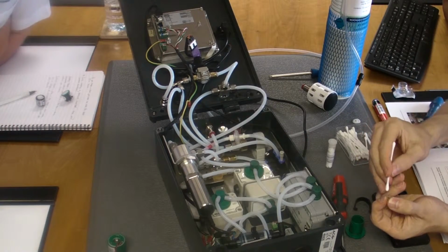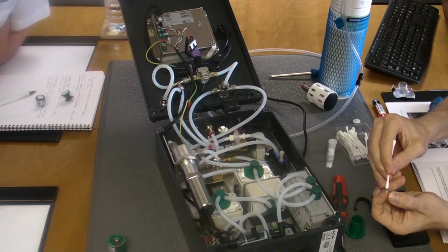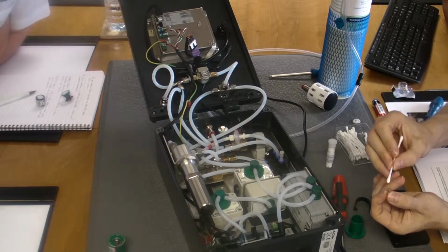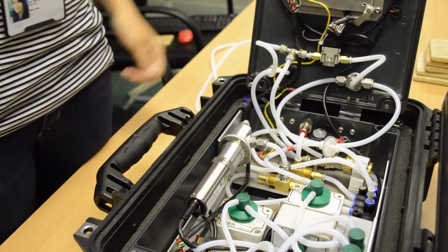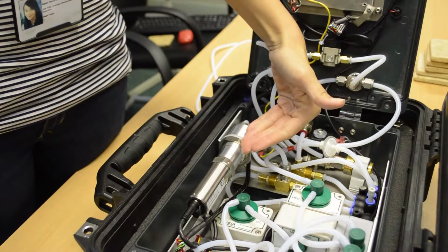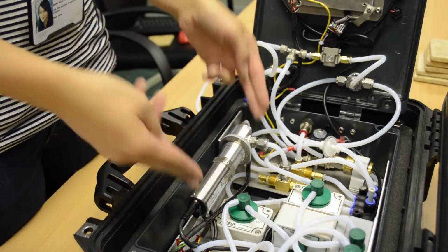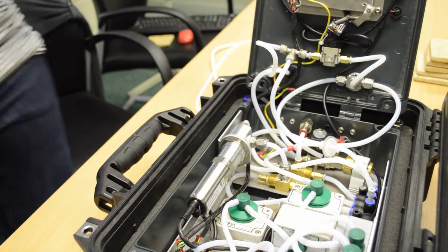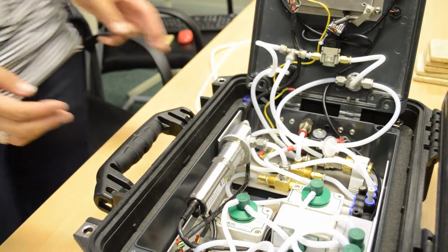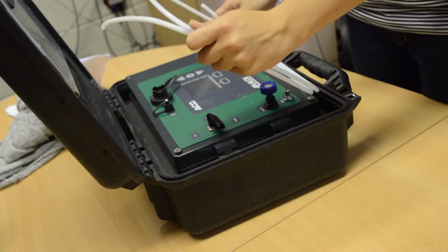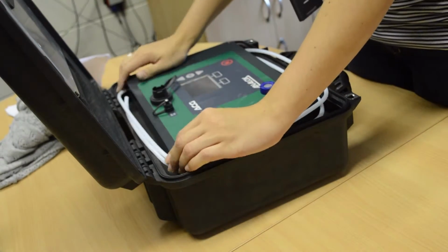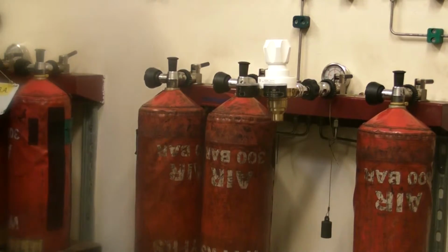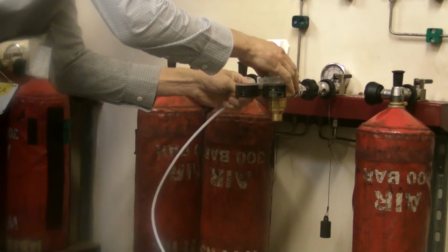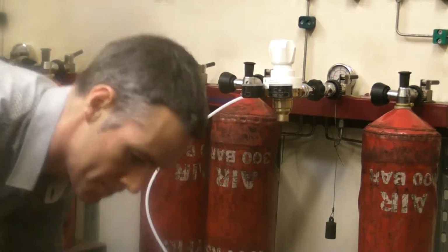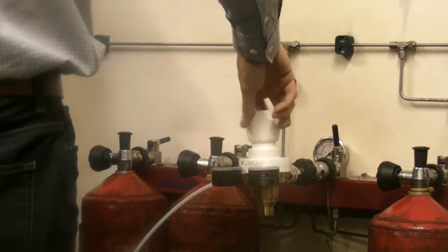Maintenance of the VOC sensor can be done by cleaning or replacing the lamp or replacing the electrode stack. The dew point sensor will require swapping out every 2 years. Once you are ready for a new dew point sensor, you can order this from Analox and we will ship you a replacement. You can then remove the old sensor and return it to us, so you are never left without a fully operational unit. The ACG Plus can now be attached to your compressed air outlet using the inlet and tube to test for any contaminants. The unit can be moved around if you have multiple compressors or fixed to the wall where the main source is.